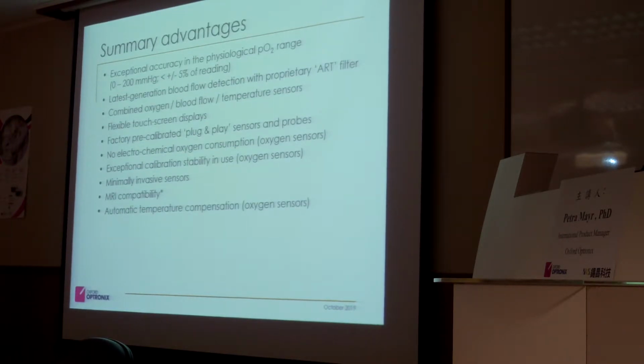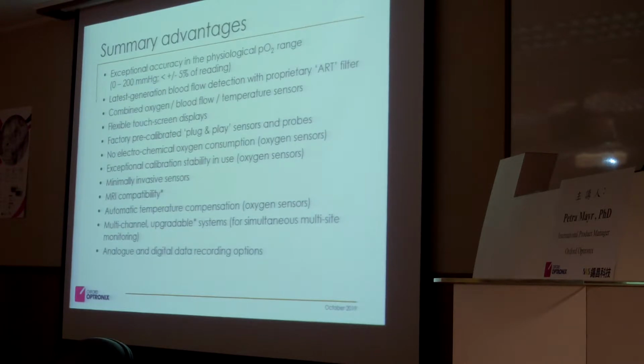As I said, we have automatic temperature compensation or manual input, and the 2-channel system can be upgraded to a 4-channel system, and you have mix and match options. For example, you might say, I want a 4-channel oxygen monitor, but I only need 2 laser Doppler. Or you just buy one and later another, so you don't have to purchase everything in one go. You can add on later. And as I also said, we have the analog output with BNC and 0 to 5 volt, or the digital output directly into laptop software from AD Instruments.